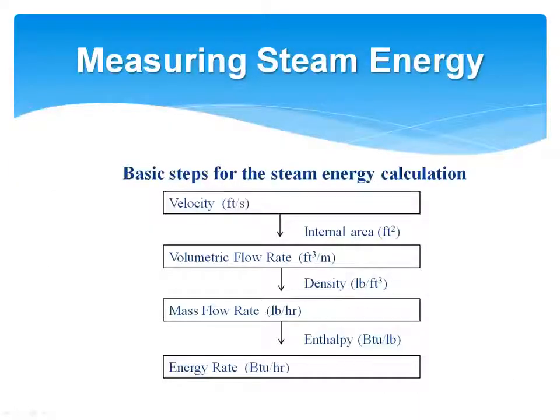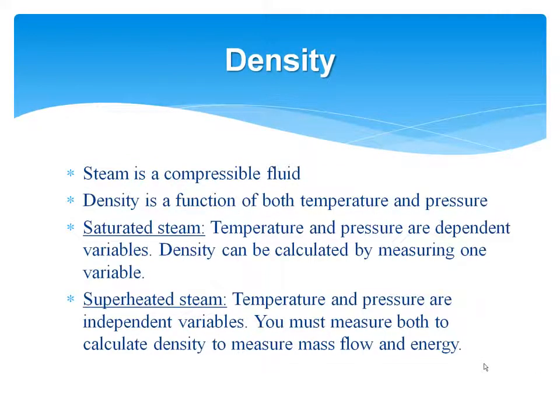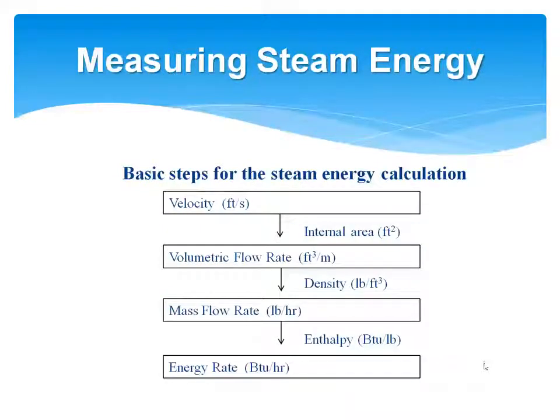I'd like to begin by reviewing what's happening inside of a typical steam meter. Most steam meters are actually velocity measuring devices, and we know the internal area of the meter, so we can get to volumetric flow rate. The actual density is required to get to mass flow rate, and we'll talk about that in the next slide. Once we get to mass flow rate, the enthalpy will tell us how much energy is actually in the steam. Slide, please.